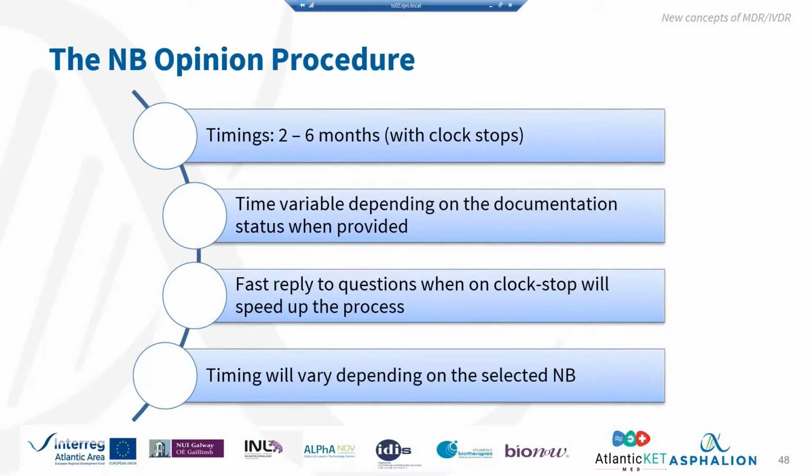But this time is going to vary quite a lot depending on the documentation status when it is provided. If you provide quite complete documentation with all the points to be assessed, such as a thorough GSPR checklist, and all the applicable standards have been identified, and all the methods to validate your device are included there, it's more likely that the procedure is going to be shorter than if you don't take this into account when doing the initial submission.